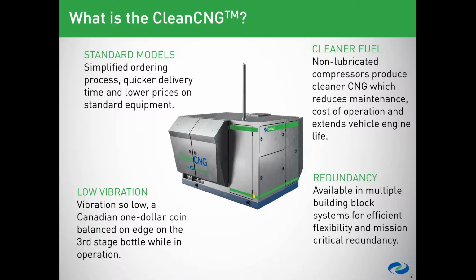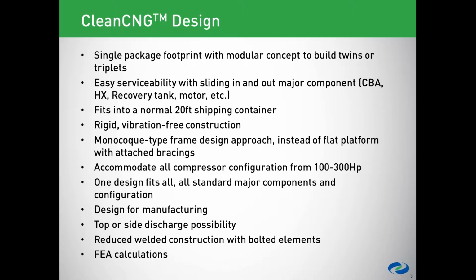Finally, this package is a modular package that can be added later on to existing installations. So for example, if there's one compressor package on site, a second one can be added in the future side by side to create a compact twin package. Some of the aspects of the new design, as I mentioned, it's a single package footprint that can be installed side by side to form twin, triple, quad. Recently we've even seen a designer incorporating our design to create a 6 compressor installation all side by side for the lowest footprint available.